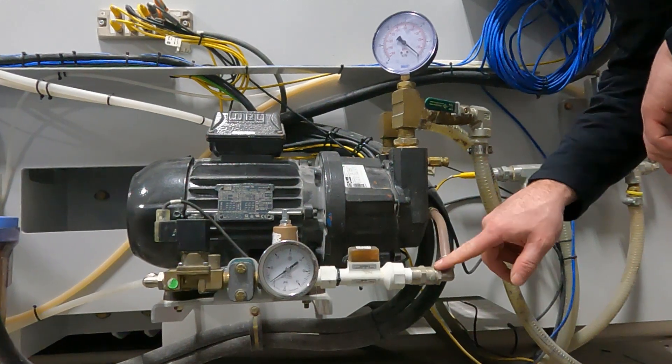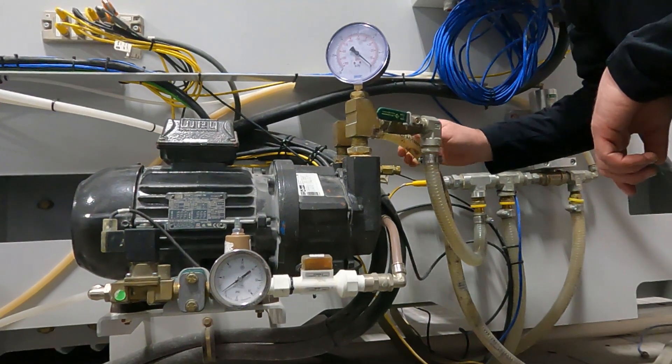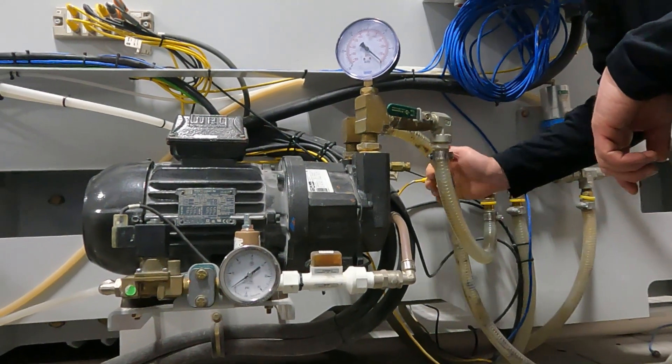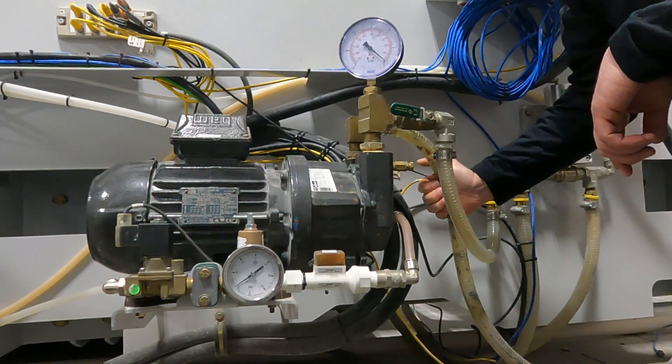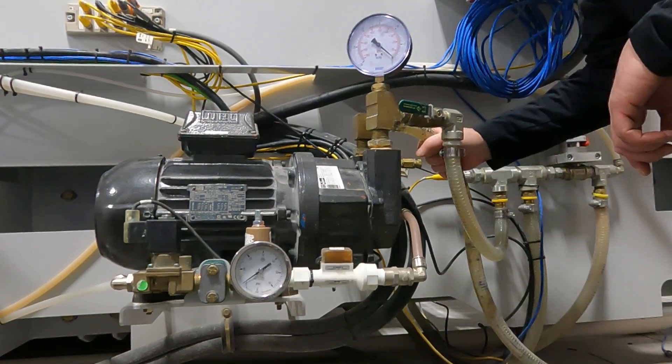The last thing to check if none of these seem clogged is your discharge line from your vacuum pump here and making sure that this is not pinched off and is open and you have good water flow going through it.